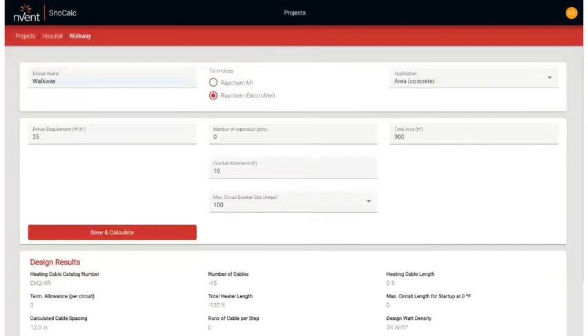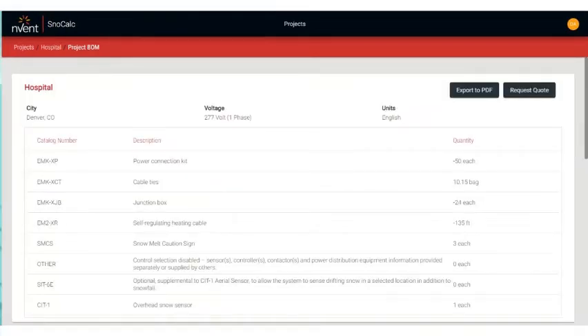SnoCalc then allows you to select which technology you prefer to use, if you have an option to use either. It then provides you with an option to override the suggested standard power output and asks for additional parameters such as the surface area to be heated, if expansion joints are required, and available maximum circuit breaker size. Once all this information is entered, SnoCalc gives you your design results and the bill of materials for your project, all available in a variety of formats.